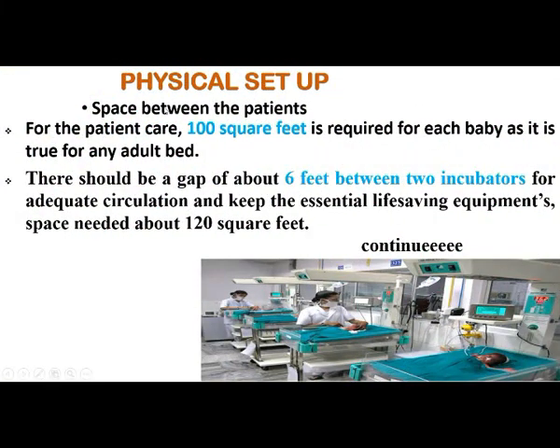Okay. Next we can see the physical setup. For the patient care, 100 square feet is required for each baby, as it is for any adult bed also. You can see the distance from each bed. And there should be a gap of 6 feet between two incubators, for adequate circulation and to keep the essential life-saving equipment. The space needed is about 120 square feet.